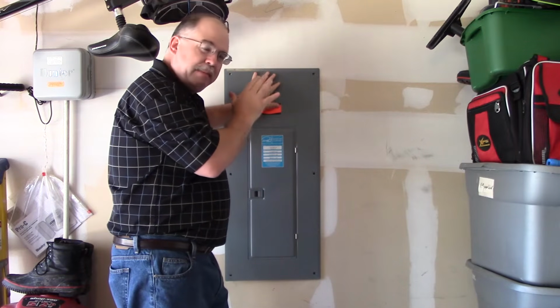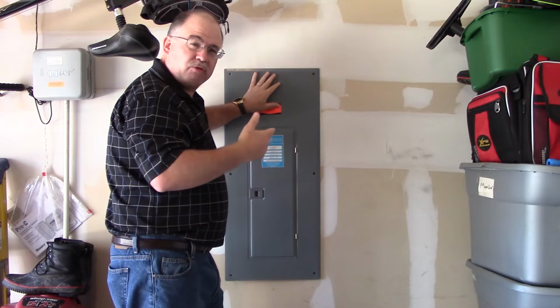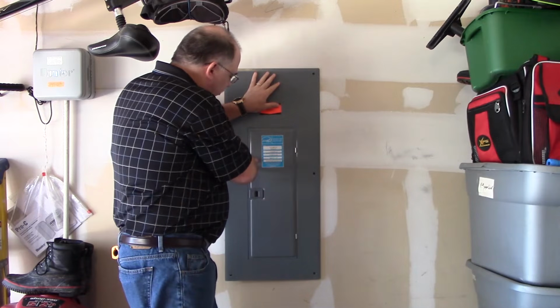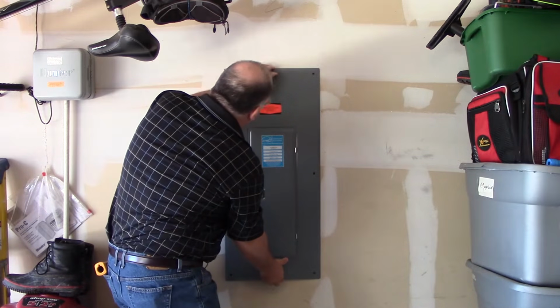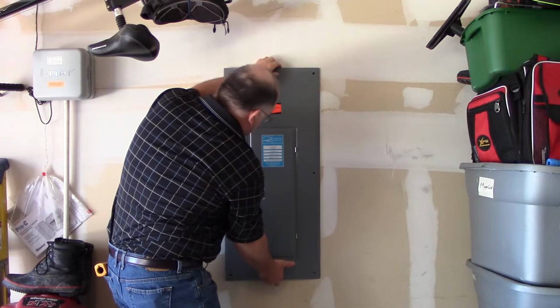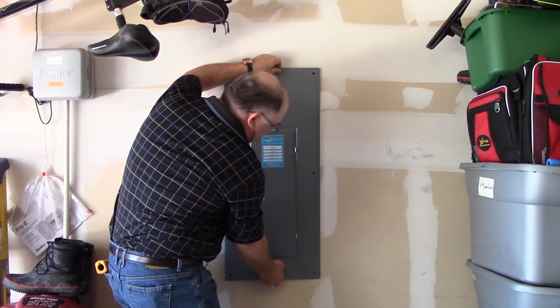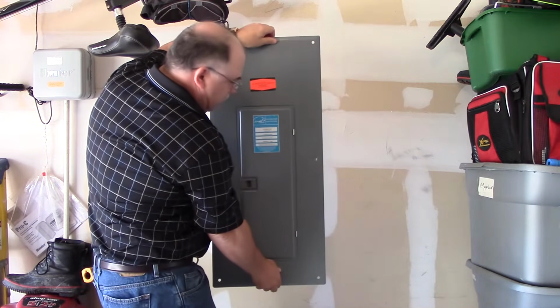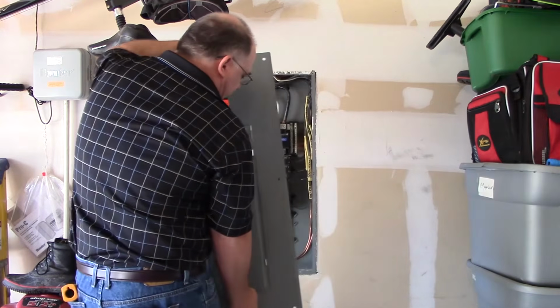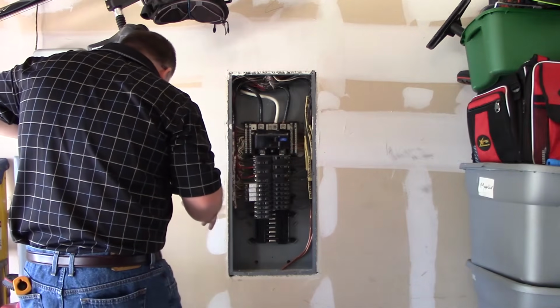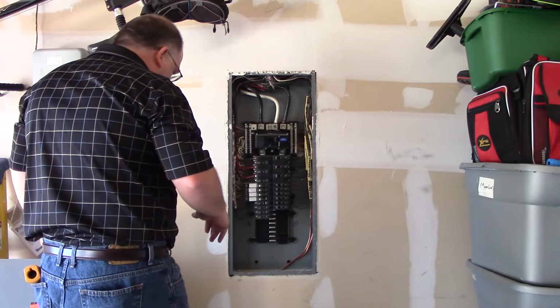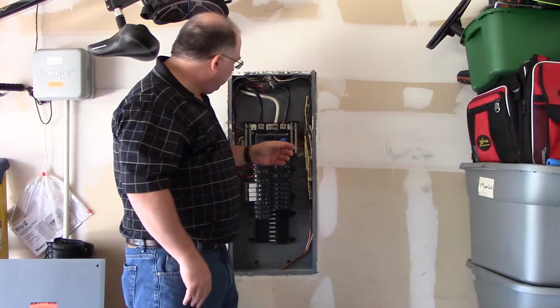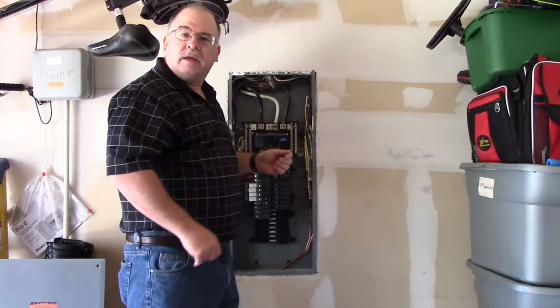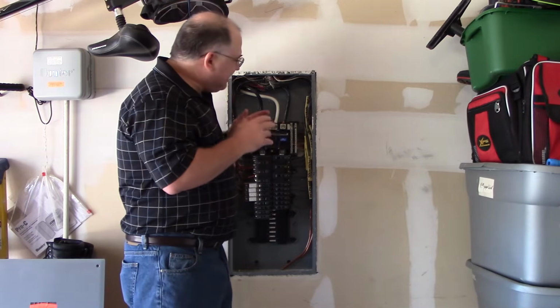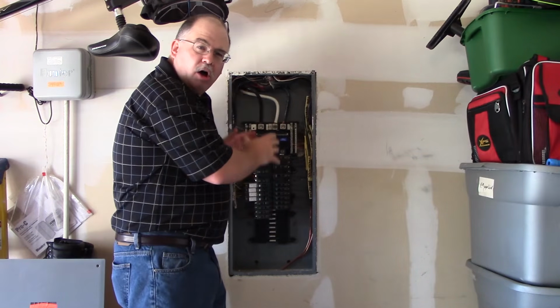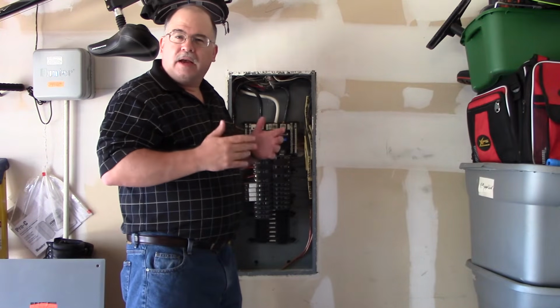Now I'm going to use it as a blast shield as I remove it. So there's an actual way to remove the cover. This door is shut. I grab it at the bottom, I support the weight, then I grab the top. Then I pull it straight off, and then I pull it away so that I'm actually protecting myself from anything that might happen in this panel. All right? So now we expose the panel. The next step is to do a detailed inspection of all the components that are in this panel, and we're going to do that next.